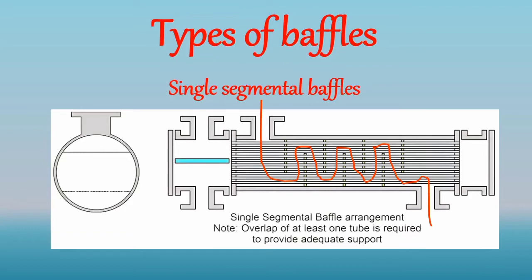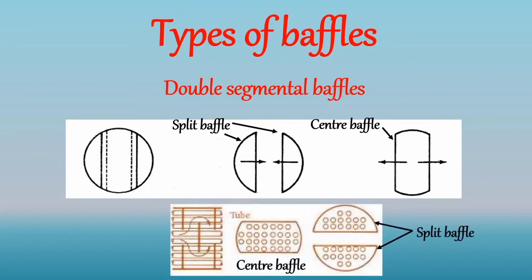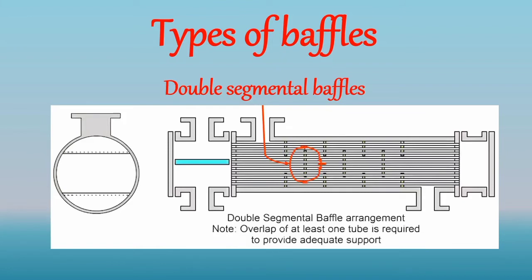The next type of segmental baffle is the double segmental baffle. In the double segmental baffle, the baffle plate is cut in such a way that we get two parts: a center baffle and a split baffle. There will be a small overlap between the center baffle and split baffle, and in this overlap minimum one tube row can adjust. Hence it is very useful in large tube bundles. These baffles split the shell side flow into two currents around each second baffle, due to which the velocity of fluid decreases, and hence pressure drop also decreases and vibrational risk is also reduced.